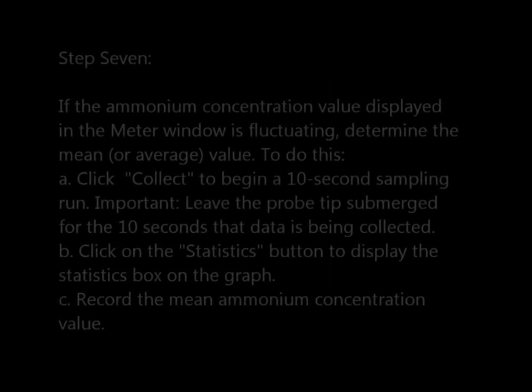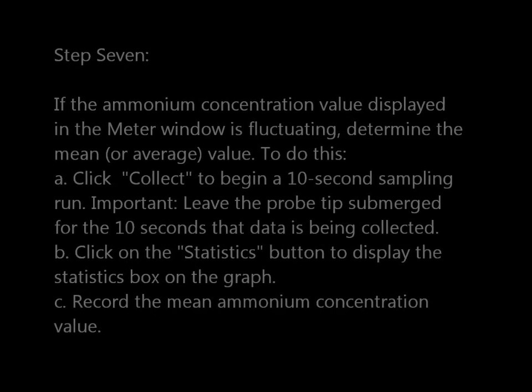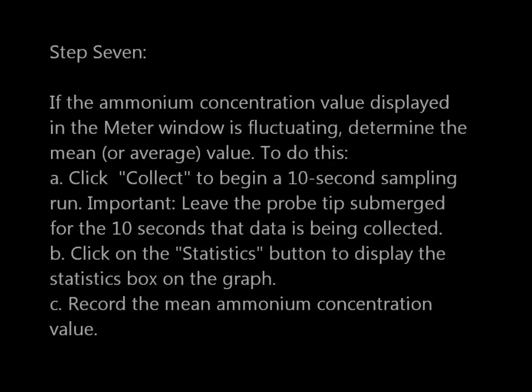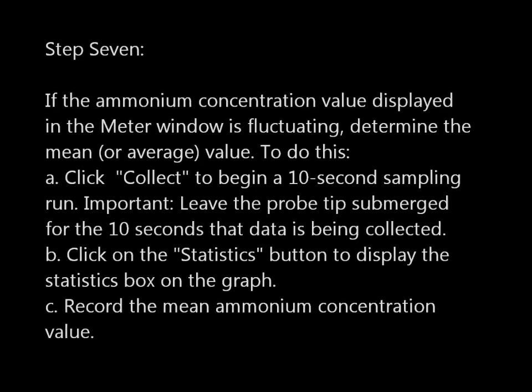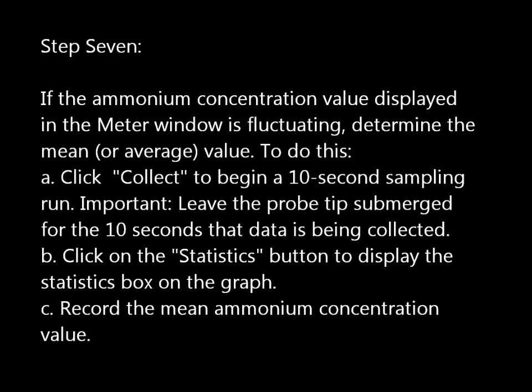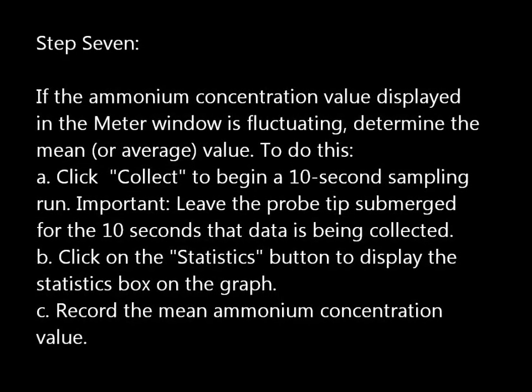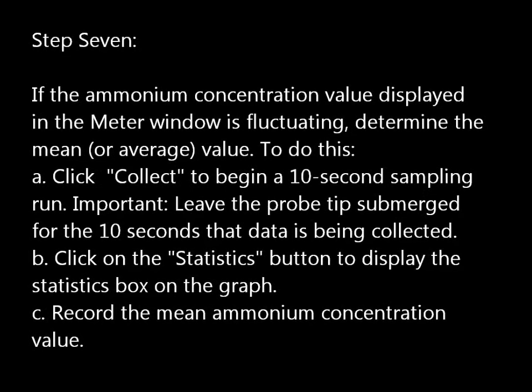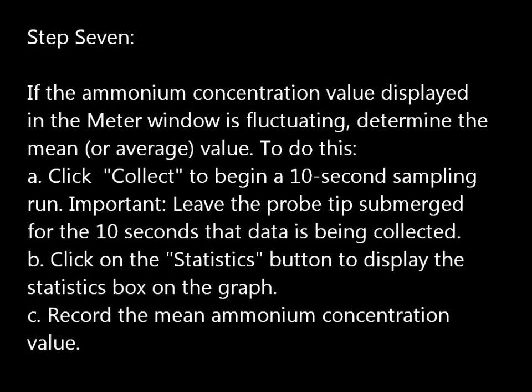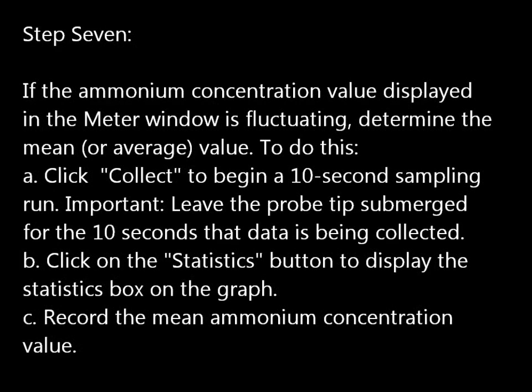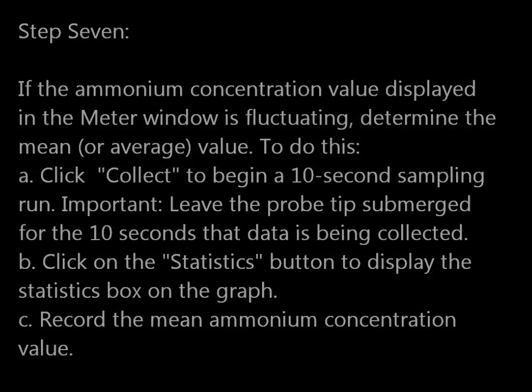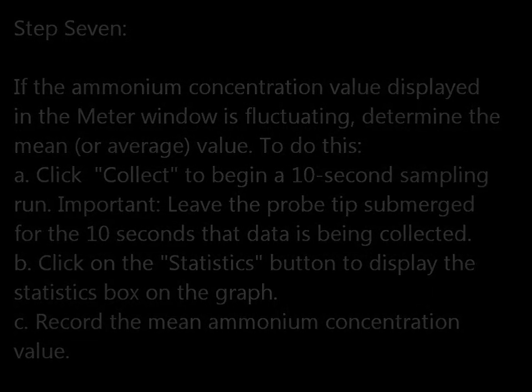Step 7. If the ammonium concentration value displayed in the meter window is fluctuating, determine the mean or average value. To do this, click Collect to begin a 10-second sampling run. Leave the probe tip submerged for the 10 seconds that data is being collected. Click on the Statistics button to display the statistics box on the graph. Record the mean ammonium concentration value.